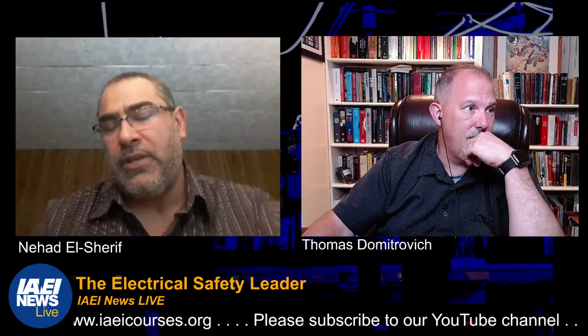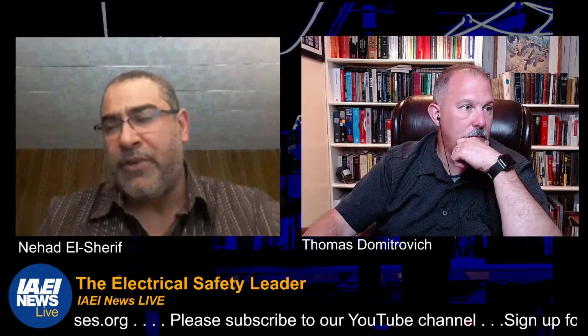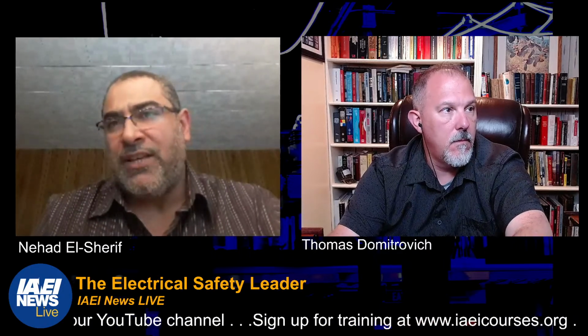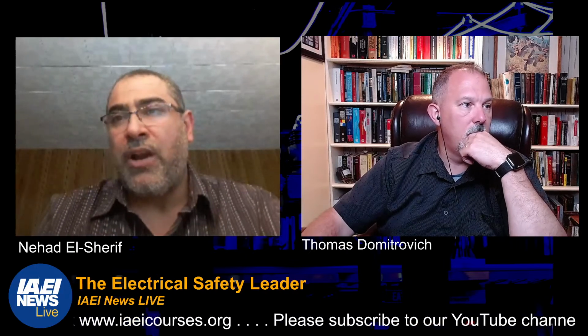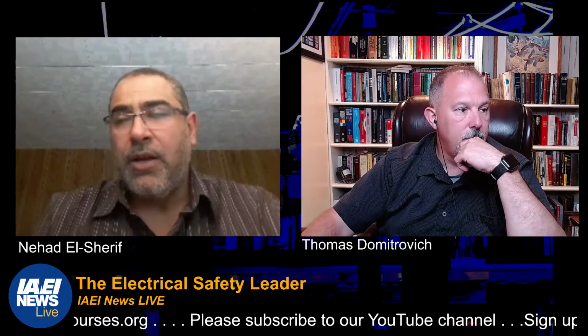And like Don identified, now we need to monitor the equipment grounding conductor of an equipment. So the change in the wiring is, I'm not going to talk commercial, but the technology that exists commercially today, maybe in the future there'll be something better. But as of now, the way to monitor the equipment grounding conductor is to run a separate circuit, called a pilot wire. You have a wire that is run from your device, let's say the source, because the device is usually installed at the source, like in a panel, like a breaker. So it's not a breaker, but it's similar to a breaker.